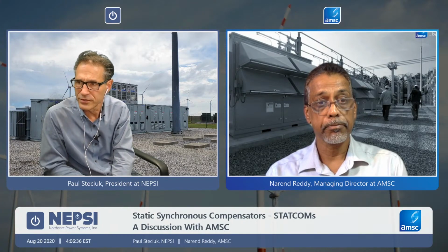Okay, so there's a question about the hybrid type STATCOMs, and this is probably directed more at NEPSI. It says, which switchgear is used to operate capacitor stages within a hybrid dynamic compensator? So in the past, what is typically done is NEPSI supplies the metal enclosed capacitor bank or filter system, and the switching device used inside that will be based upon system voltage and what's best for the project. So the switching device that's chosen is based on MVAR rating, voltage rating, and what's most appropriate for the project. Generally speaking, it's not switchgear, but rather a switching device, and that could be a capacitor switch, a pre-insertion resistive type switching device, or a standard breaker with a C2 rating. There are several different options, but typically it's not switchgear, but rather a switching device, and it's installed within the metal enclosed system itself.